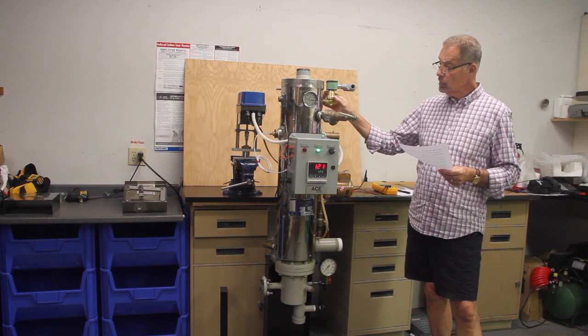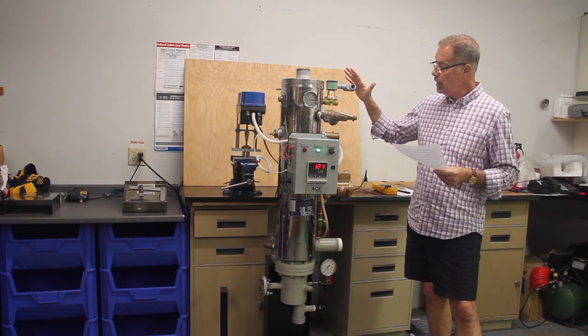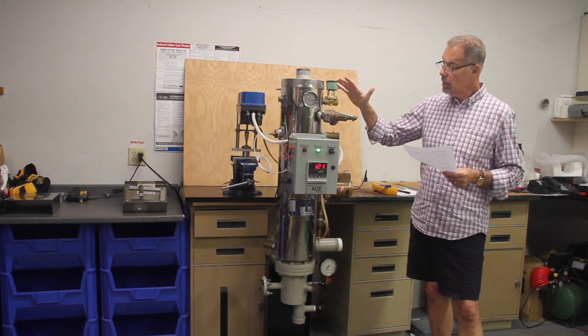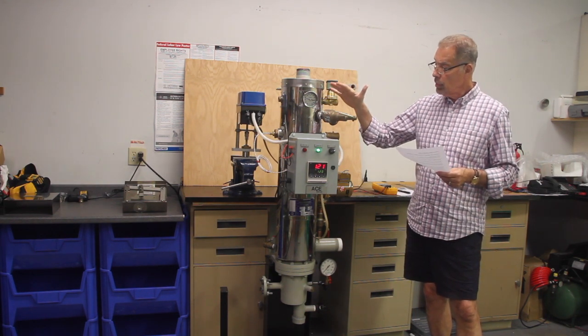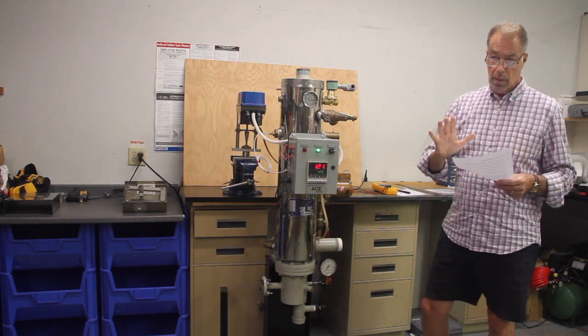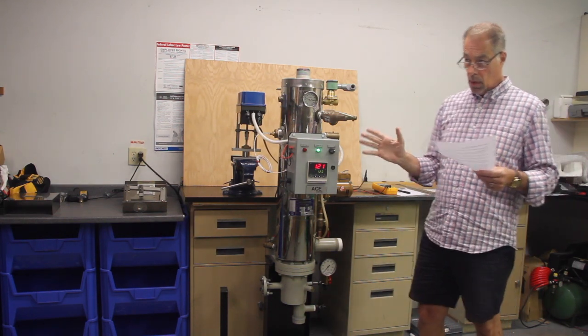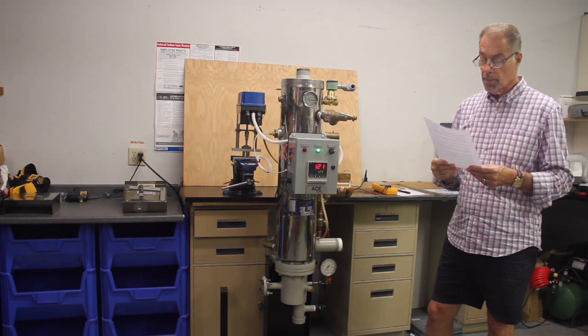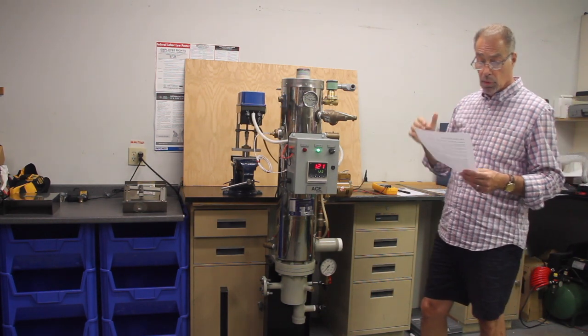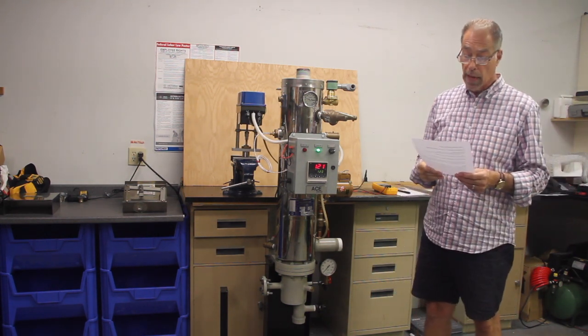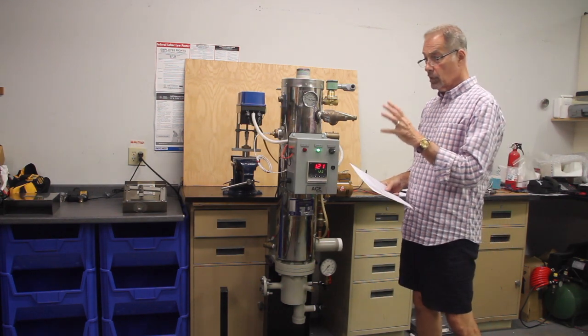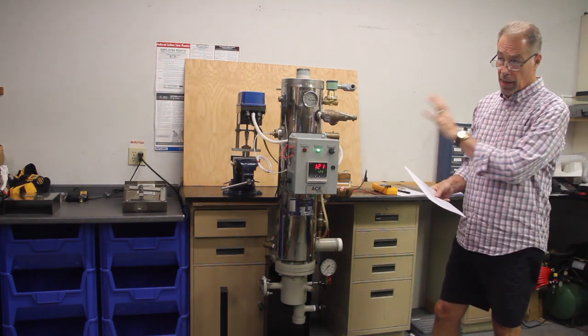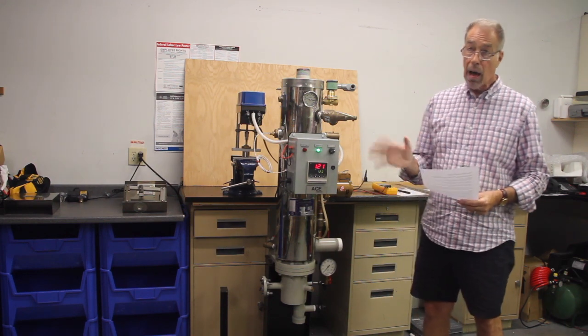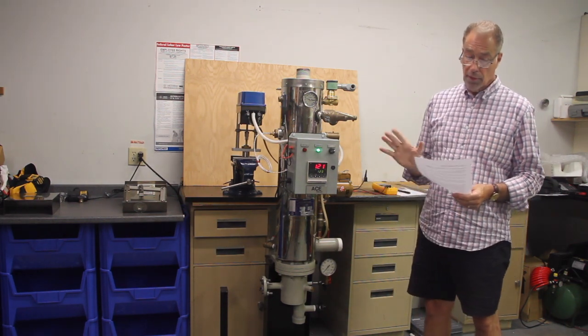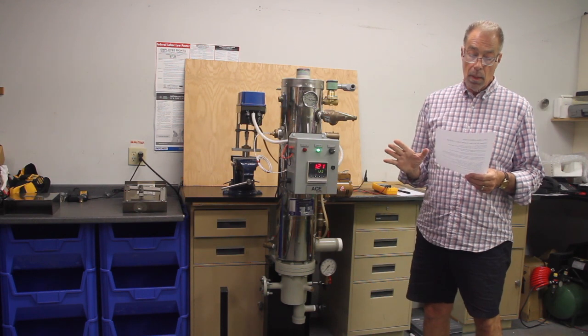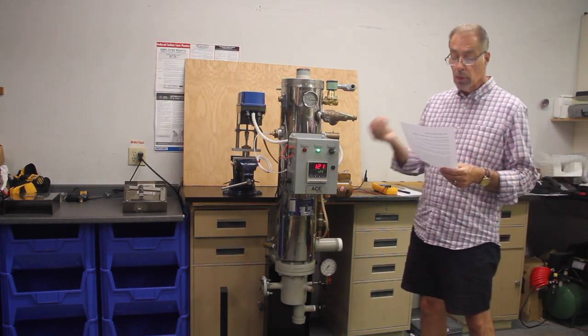It's a temperature safety system that is working in concert with the controller and the relief valve to prevent any over temperature condition to the building. And also, I believe, I'm sure that in this installation there's also a blending station on the wall that's not in our scope, that will not allow hot water to get to the facility and maintains the right building recirculation water.